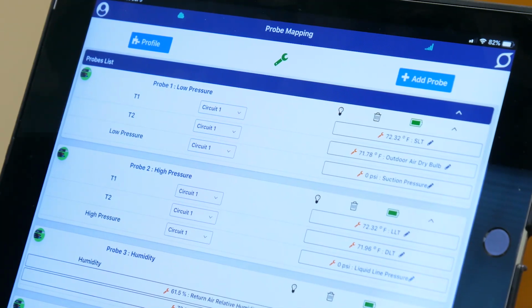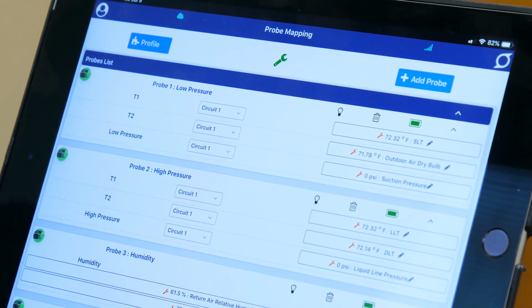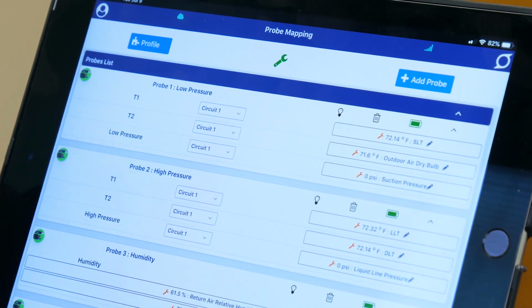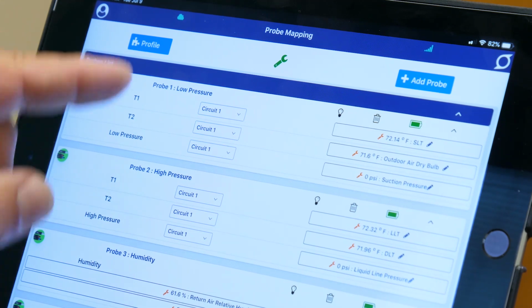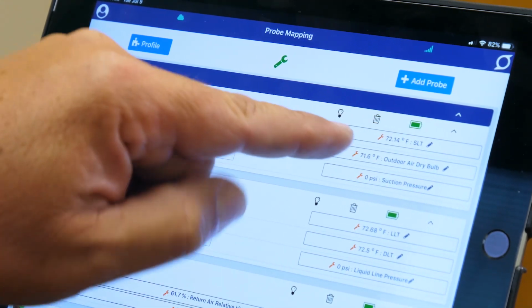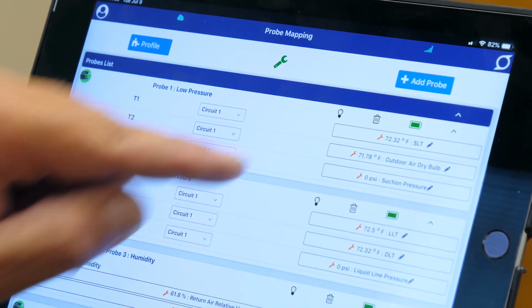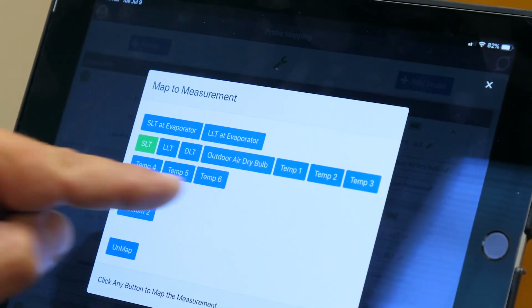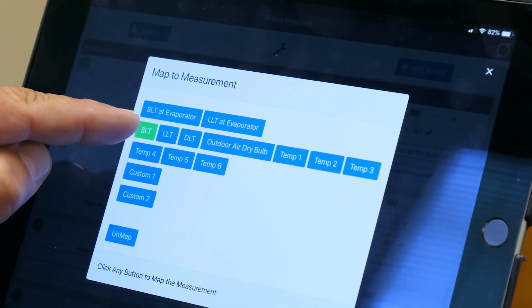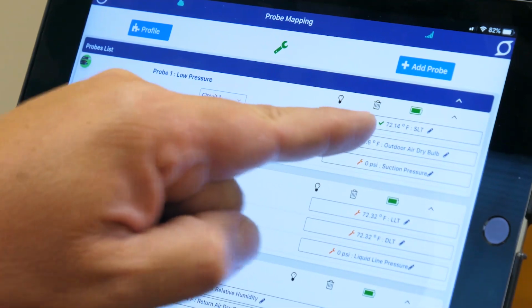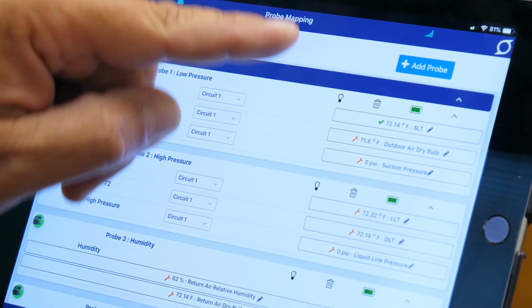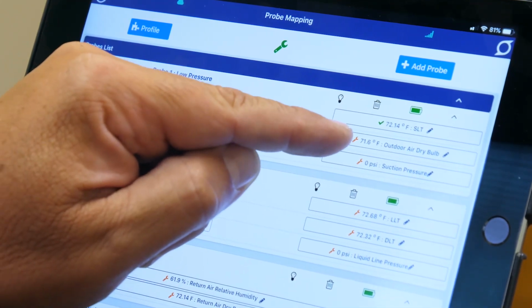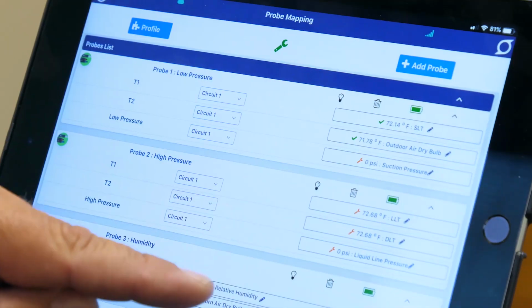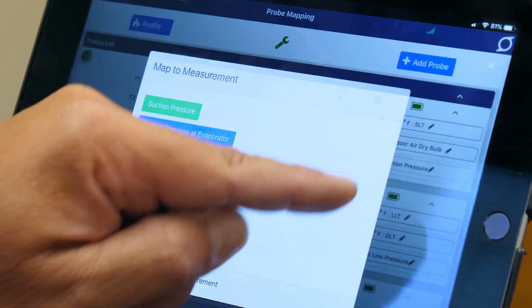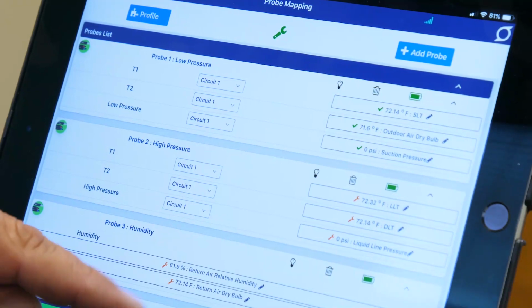So now that all of our probes are mapped and present and ready to go, now we're going to just verify all of our values to make sure that we're getting all the measurements that we actually need. On the low pressure side, our suction line temp, as you see, we have a little red wrench here. We're going to tap that and just verify that that is actually what we're looking for. Yes, we're looking at suction line temp. That gets a green check mark. We're going to go down the list here on each one. Our outdoor dry bulb, and of course our suction pressure here.